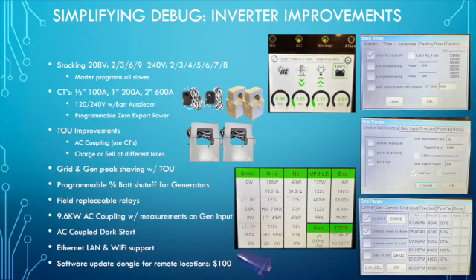But that's a big challenge with AC coupled panels. If you drain the battery completely on AC coupled panels, you can't recharge the system because those panels require a reference. So we implemented AC coupled dark start, which allows a small reserve in the battery. It's quite impressive how it works - basically it waits until the next day and then fires up the inverter for a short period.